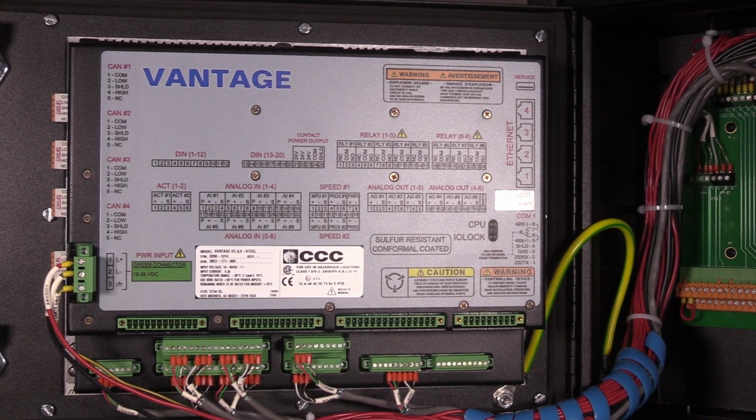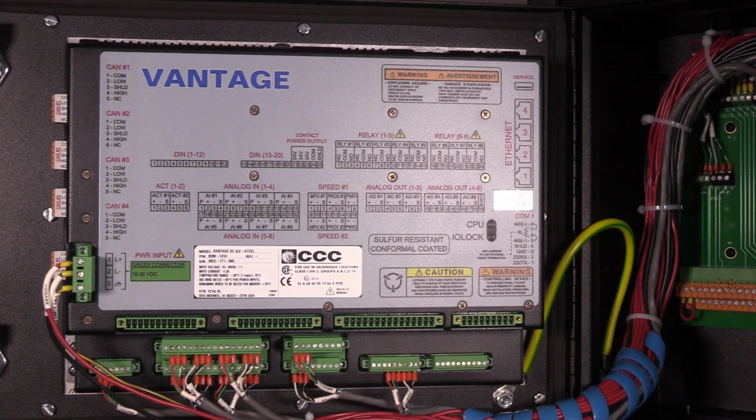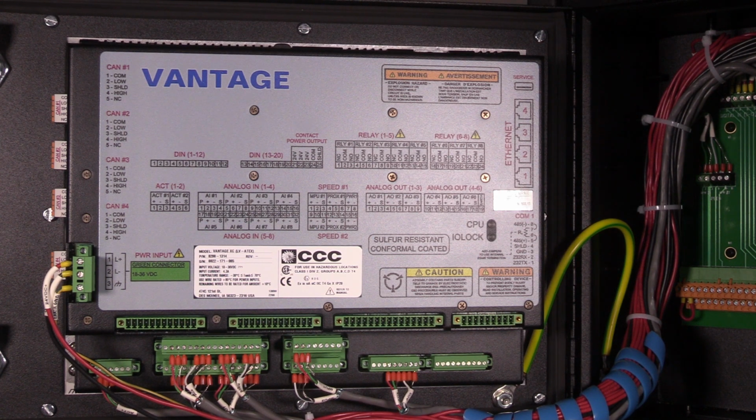The next type of signal is a speed signal. Each channel on the controller is isolated from each other and may be configured for either magnetic pickup units, or MPUs, which serve as a passive signal, or for proximity sensors, which serve as an active signal. An isolated proximity power of positive 24 volts is provided on each channel for proximity sensor use.